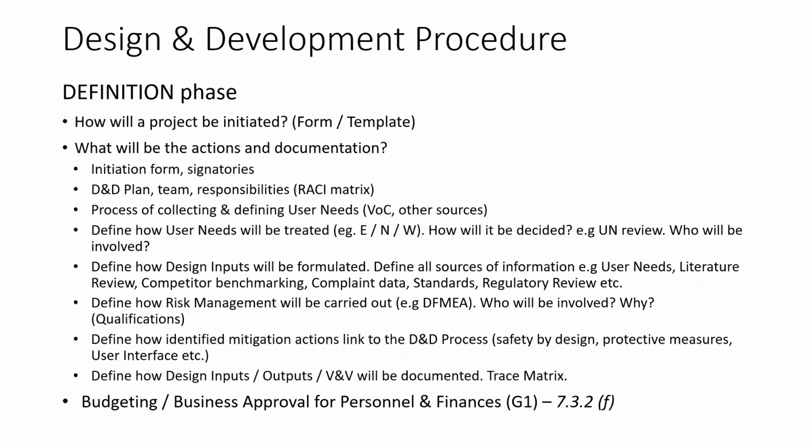Would a user only be a clinical user? Would it also be a distributor, for example? Would it also be a hospital nurse? Would we talk to a hospital administrator? Who are all the stakeholders? Would we have focus groups? Would we speak to only individuals? Would we do interviews? So what are all the methods that would be followed in creating the design inputs? What are the standards we would refer to? Will we do competitor benchmarking? If we do competitor benchmarking, how will we define competitor attributes? Would we access complaint data from anywhere, from external databases, for example? Would we look at standards?